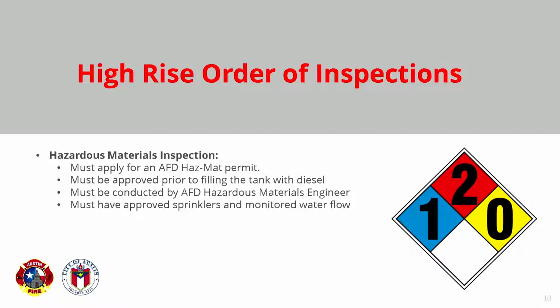So this is one of those scenarios where it's critical that the ownership applies for the hazmat permit, and then you have to get on board with getting this inspection. If it's an interior generator, you're going to have to be inspected by an AFD hazmat engineer. Hopefully they're under 660 gallons. Whole other can of worms if they're not.